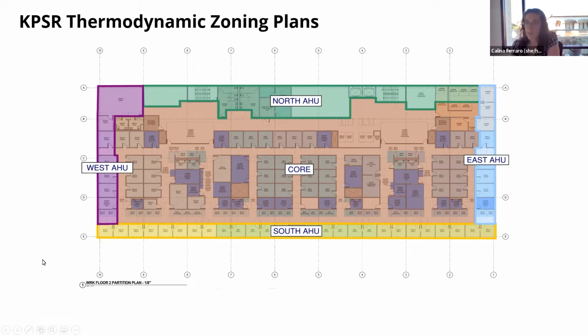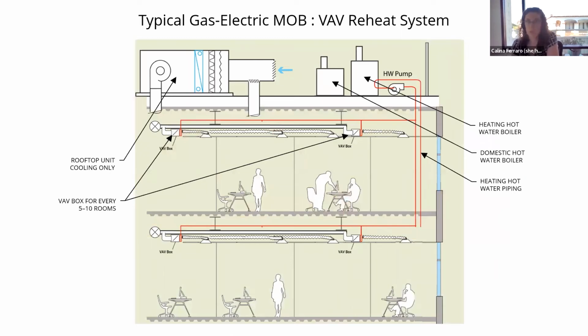So then looking at what that means on the system level. This is what that conventional system would look like, right? We would have a rooftop unit that's going to need to do cooling for that interior zone all the time. So you've got a cooling coil in that unit, and we supply that to this full space. That would be that original typical box model where we have two big boxes. We're going to have a unit that does the cooling, and then separate from that, we would conventionally have a gas boiler that connects to a heating hot water piping loop that then circulates heat throughout the building with hot water to reheat. So the air coming through this duct gets cooled off first at the unit and then gets reheated by that coil in those perimeter zones where we need to do it.